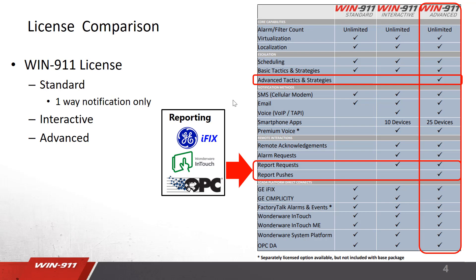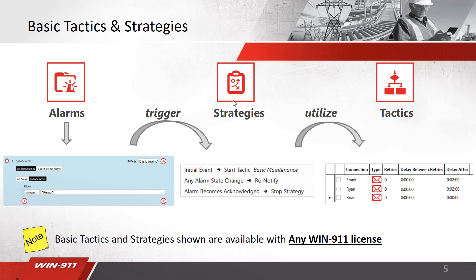On the next few slides, I'll compare the basic tactics and strategies to the advanced tactics and strategies. Basic tactics and strategies are available on any of our licenses. A rundown of how our software works: your alarms trigger a strategy, and then that triggers a tactic. Your alarm comes in, it's filtered using that dynamic method — here we're filtering on the word 'pump', so anything with the word pump will be brought into this basic maintenance strategy. A strategy is a policy that defines your starting, stopping, and re-notifying. This strategy points to a tactic. When this basic tactic goes off, we will email Frank, wait two minutes, email Ryan, wait two minutes, and eventually email Brian. It's straight down the list, standard configuration. You can also configure a delay before notification and retries.